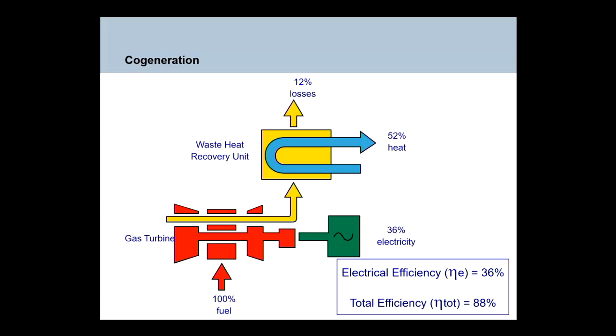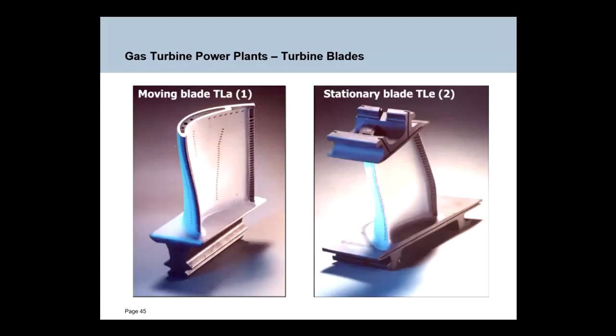Okay. In Europe, this is used quite often where they use the waste heat for district heating. So they'll have a gas turbine power plant in the middle of a city, burning natural gas, and the waste heat is used to heat buildings in a number of city blocks. And it becomes very efficient, so you can get up to 90% heat utilisation by doing this sort of thing. Very efficient way of using heat.